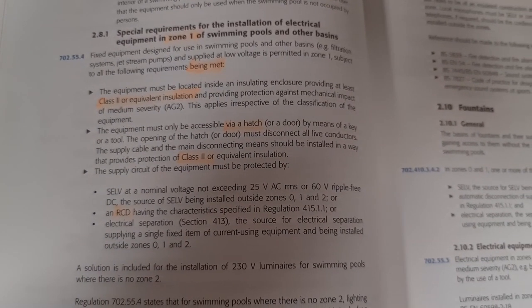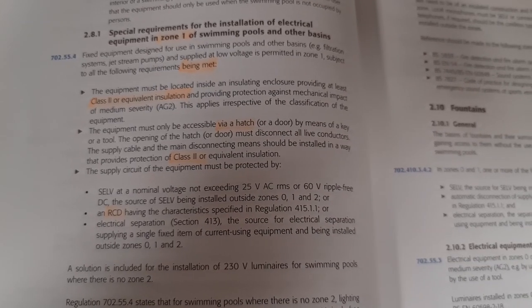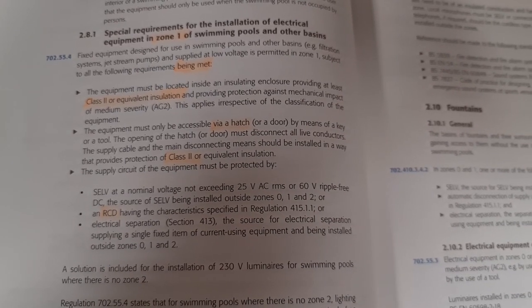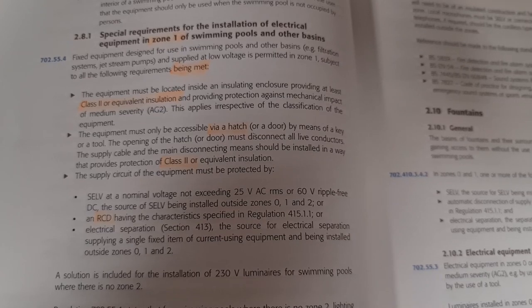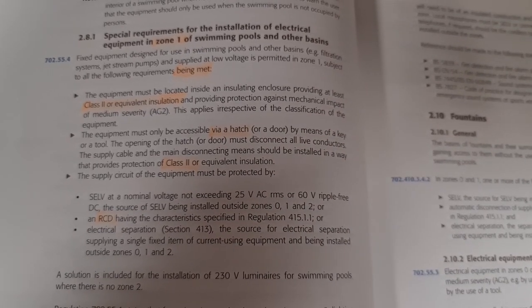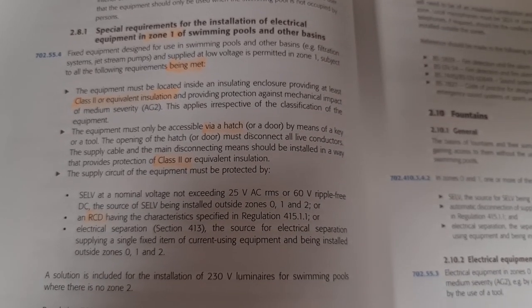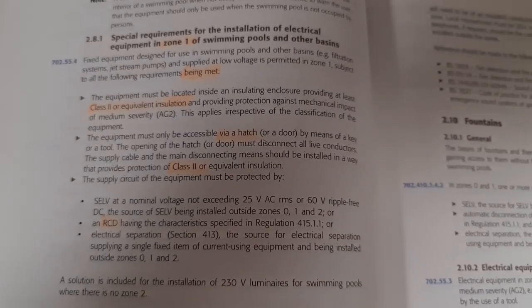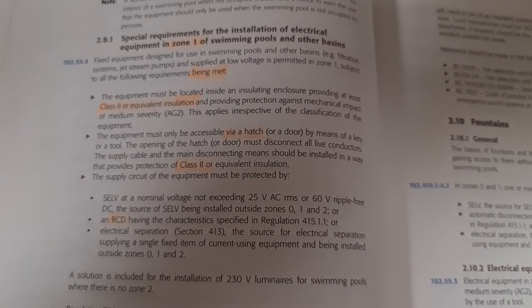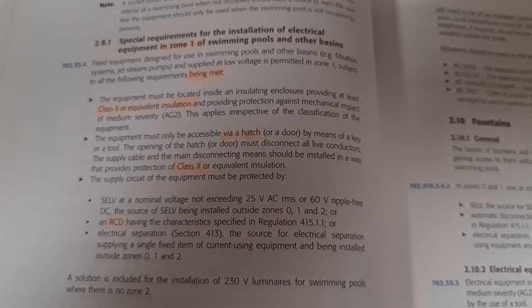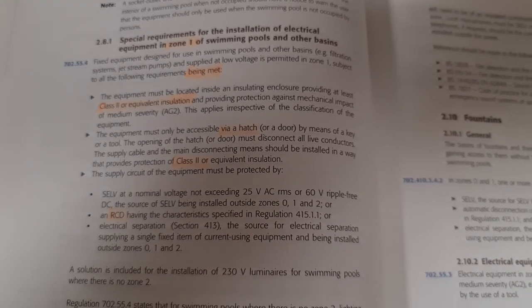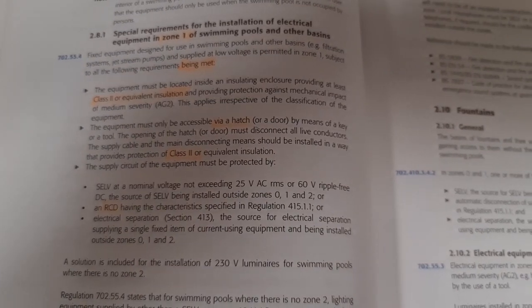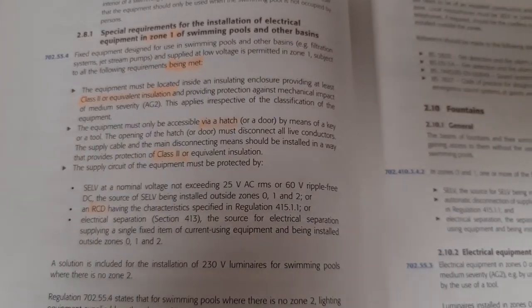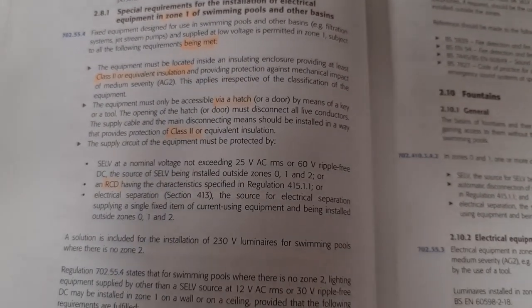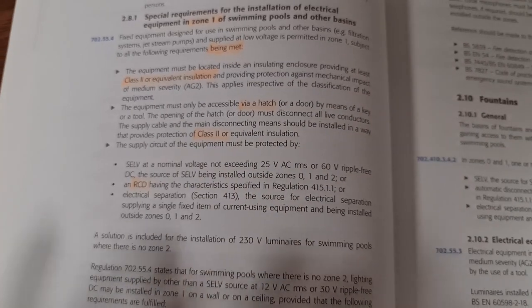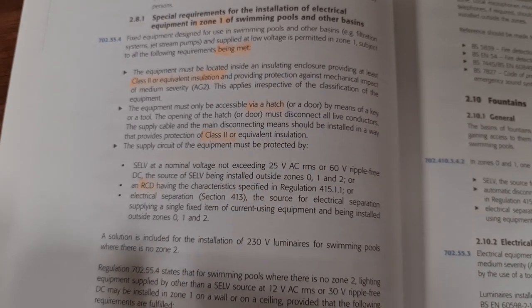Looking at fixed equipment designed for use in swimming pools and other basins, like filters, typically found underneath a hot tub within zone 1, the equipment must be located inside an insulated enclosure providing at least class 2 or equivalent insulation. This is why the product standard should be followed, because the product standard for a hot tub could say something entirely different to this. But this is the actual guidance to section 702.